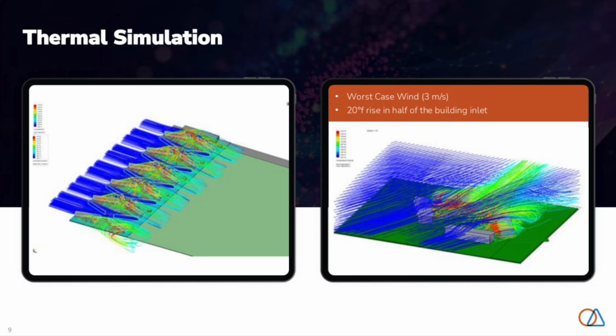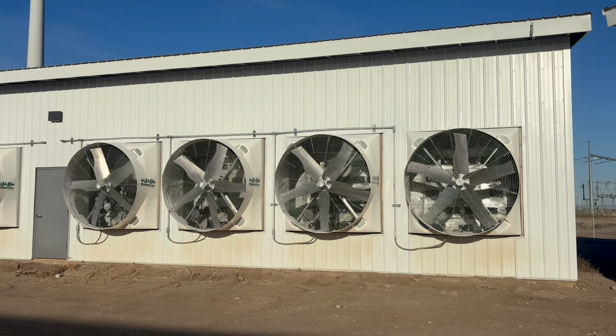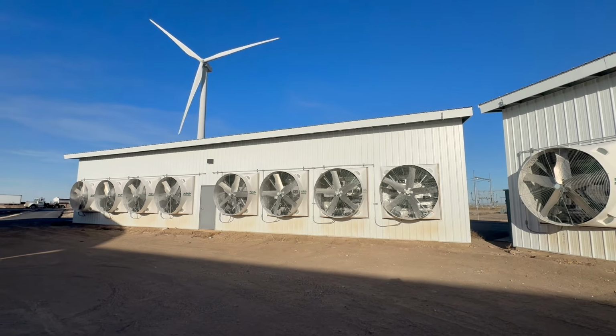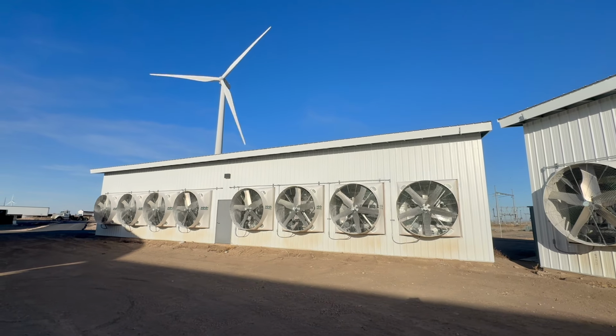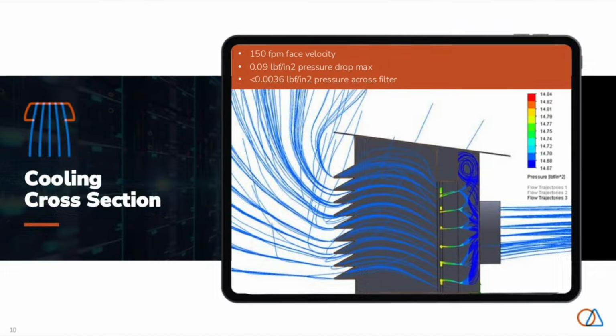So look even at the thermal simulations here - these windmills are able to turn 360 degrees. They analyze the wind flow for the entire year and optimize the site so that every single side of these data centers is getting pure airflow. We walk through the center of the diamond, that's essentially the hot aisle, and you can really feel the temperature change. Looking at these thermal simulations, the cooling cross section, you can tell there's a tremendous amount of foresight put into this build.